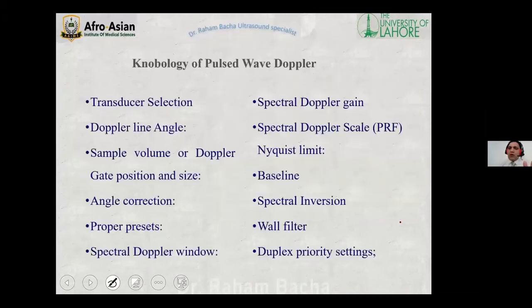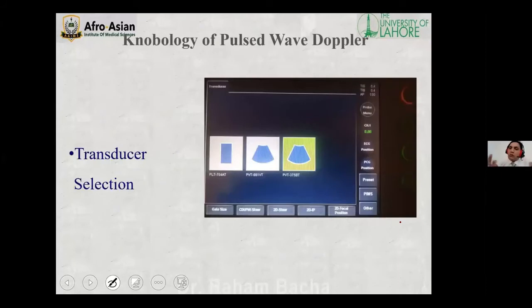So whenever we apply spectral Doppler, first of all, a Doppler line will appear on our screen, and there will be two parallel lines or bars on it. That will be the sample volume or Doppler gate. We are going to discuss it, but in the settings, we have first of all to select the transducer. That transducer selection could be done with the help of presets. Whenever you select the proper presets, the proper transducer will already be selected.